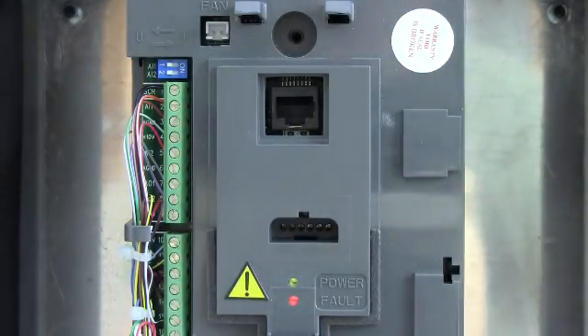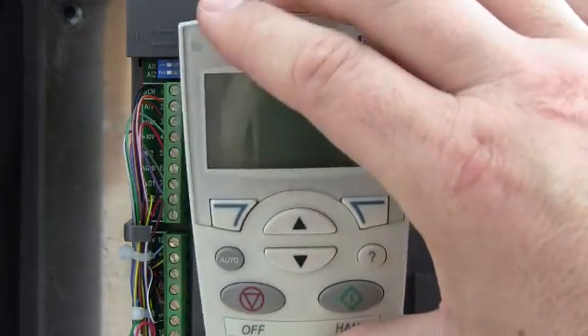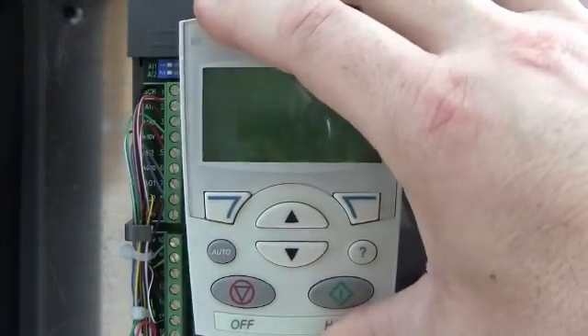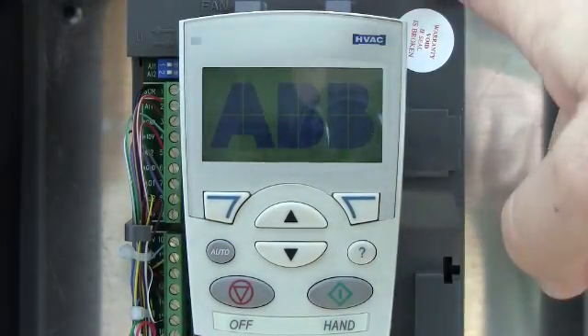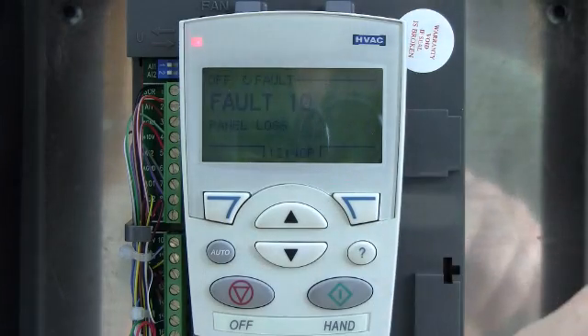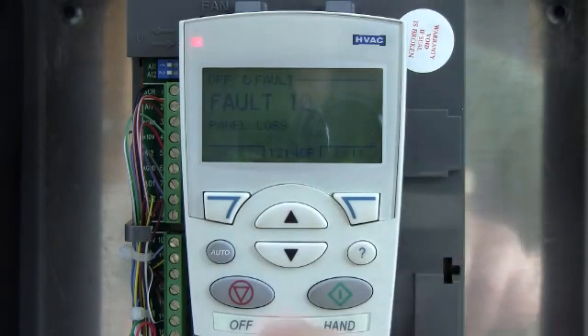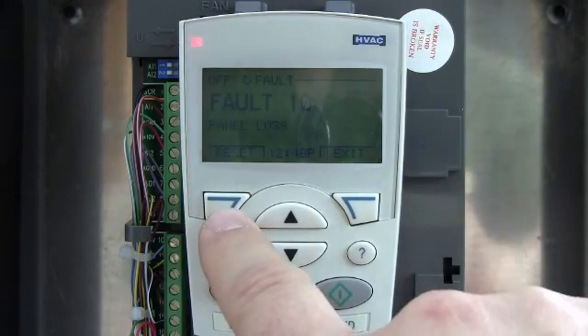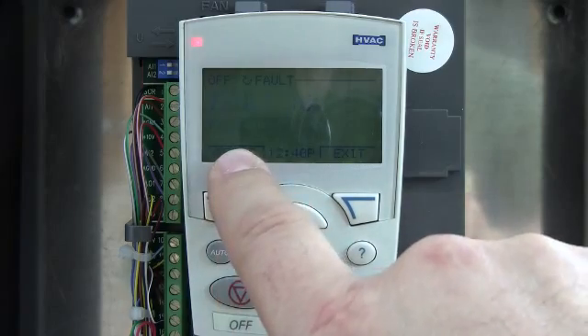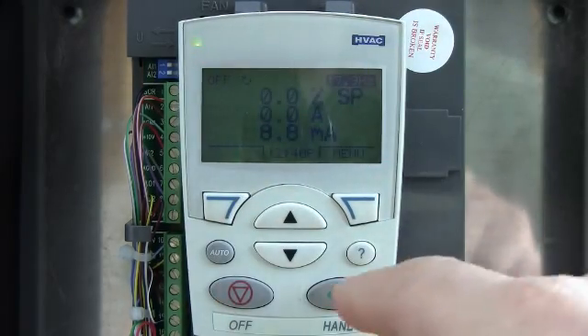So right now the drive is tripped. I wanted to do a quick fault demo and also go over the fault logger in the main group to show you the drive's diagnostic tool, and then also how to reset it. 99% of the time the reset button is this soft key right here on the left — it says reset right there, so just hit reset and we're good to go.